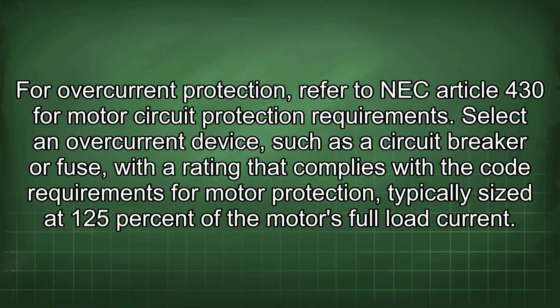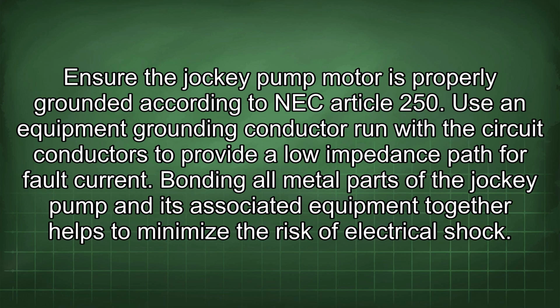For overcurrent protection, refer to NEC Article 430 for motor circuit protection requirements. Select an overcurrent device, such as a circuit breaker or fuse, with a rating that complies with the code requirements for motor protection, typically sized at 125% of the motor's full load current. Ensure the jockey pump motor is properly grounded according to NEC Article 250. Use an equipment grounding conductor run with the circuit conductors to provide a low impedance path for fault current.